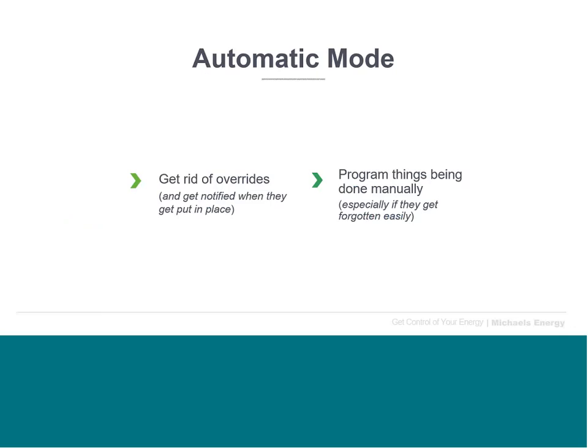My first recommendation here would be to do some kind of notification system, so that if an override's been in place for a certain amount of time, you get a notification to go back and remove that override and get the system operating back into a more automatic mode - or just have the overrides only be temporary in order to prevent them from doing any lasting harm. Sometimes overrides are the quickest and easiest way to fix a problem, so we don't necessarily want to get rid of that capability. We just don't want the changes to make lasting impacts on utility consumption.